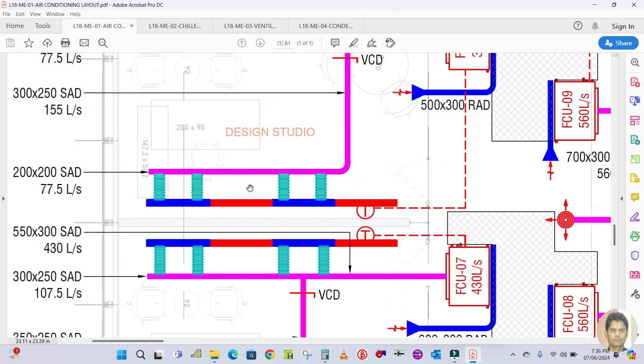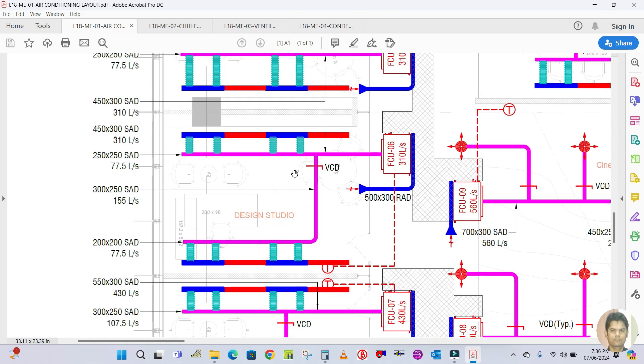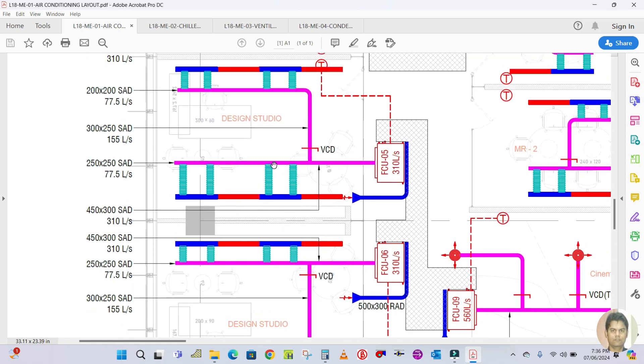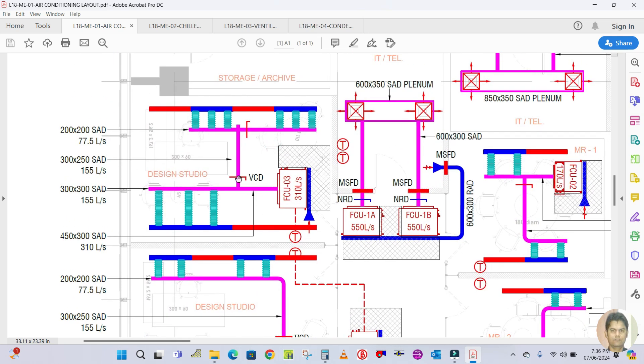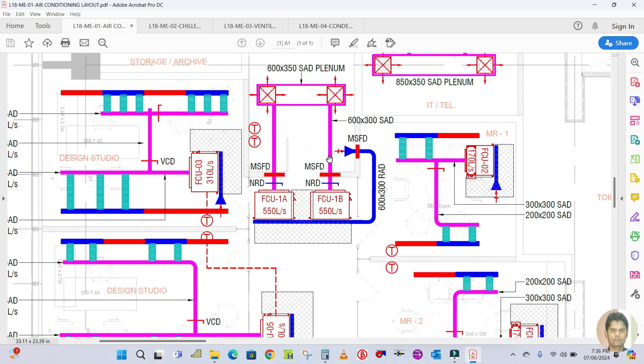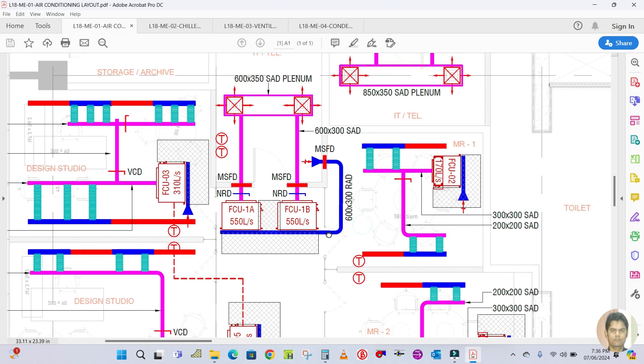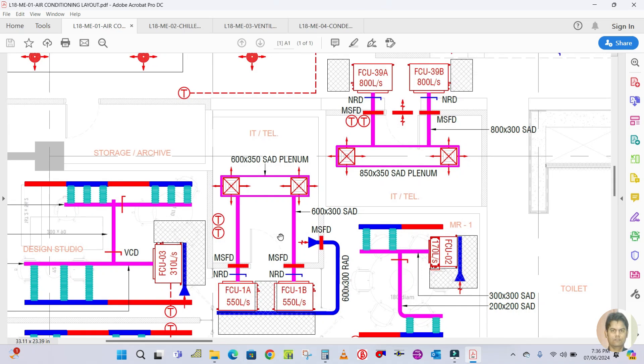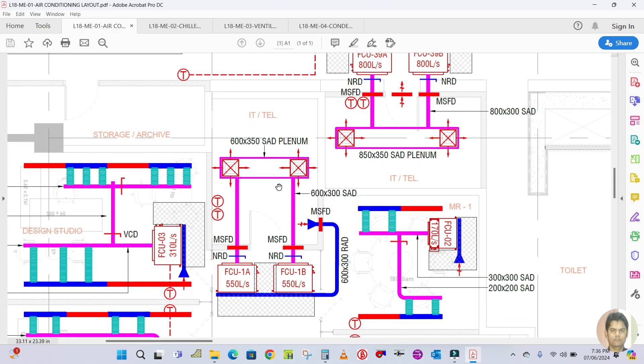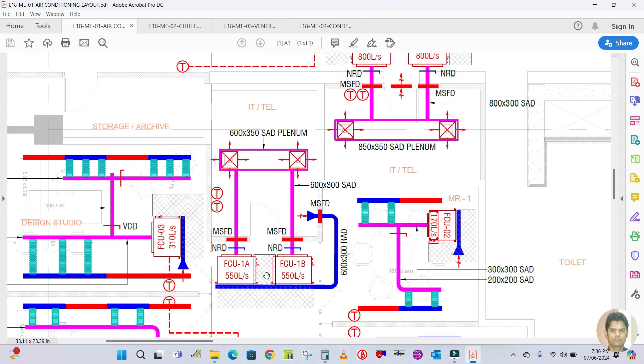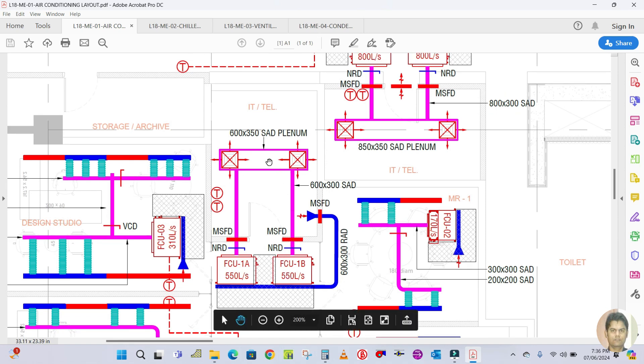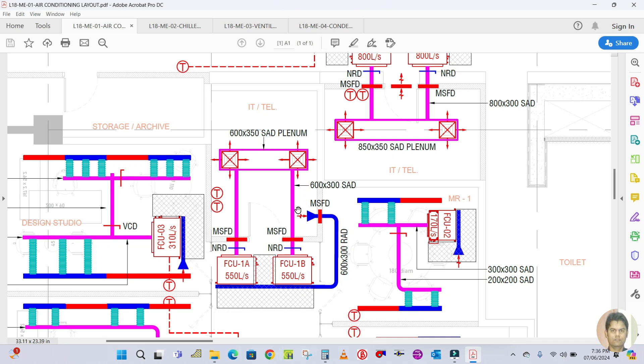For this design studio we supply the air with slot diffusers only. There is another design using square diffusers — in the telecom room. Two FCUs are there, and both FCUs are connected to a main plenum box. The supply duct size is 600 by 300, and the plenum is 600 by 350.